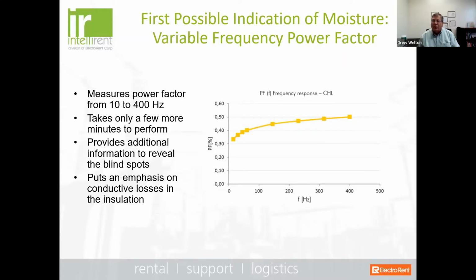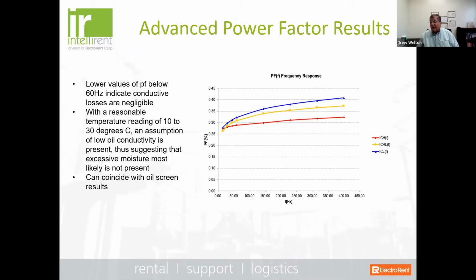So what can we do in our power factor test to take a look at what could be possible conductive losses? Well, we know in the industry that rather than just doing a standard 60 hertz power factor test, we now have the capability to extend the frequency range of that measurement. And this would take only a few more minutes to perform, and provide some additional information to reveal what we call blind spots. And when you do a power factor measurement at a lower frequency range below the 60 hertz, this puts an emphasis on conductive losses in the insulation.